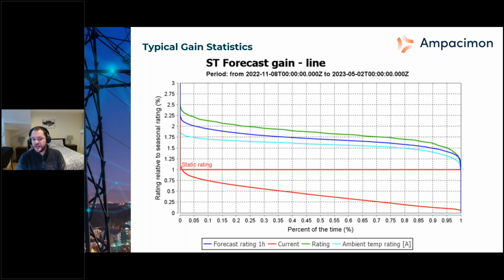At the end of the day, what I have here is my static rating at 100%, and I can get my ambient adjusted rating or ambient temperature rating in light blue, then my DLR rating in green, and then a forecasted rating of the DLR in blue. You'll note the forecasted rating is a little bit lower than the DLR rating in real time.